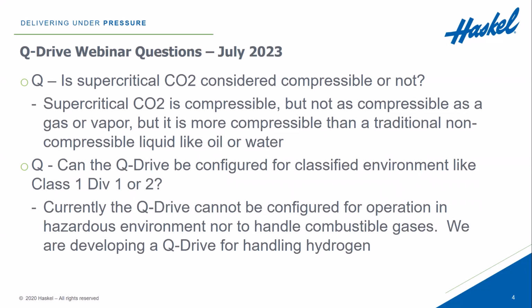Is supercritical CO2 considered compressible or not? Supercritical CO2 is somewhat compressible, not as compressible as a gas or a vapor, but it's a lot more compressible than a traditional non-compressible media like oil or water. So it is somewhat compressible, but it's somewhere in between. It's only compressible by a factor of maybe 1 or 2 compared to gases, which are substantially compressible, or water, oil, which is almost incompressible.